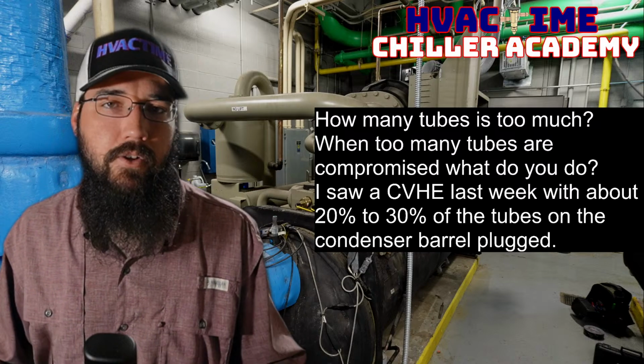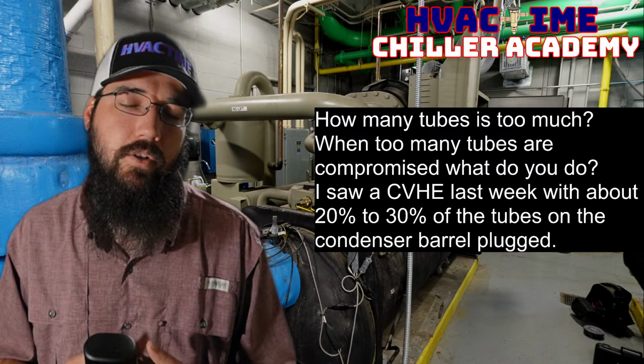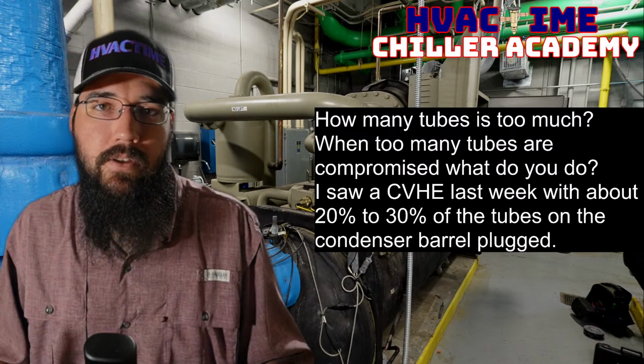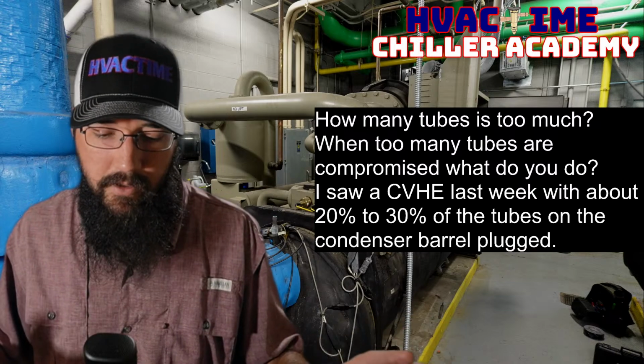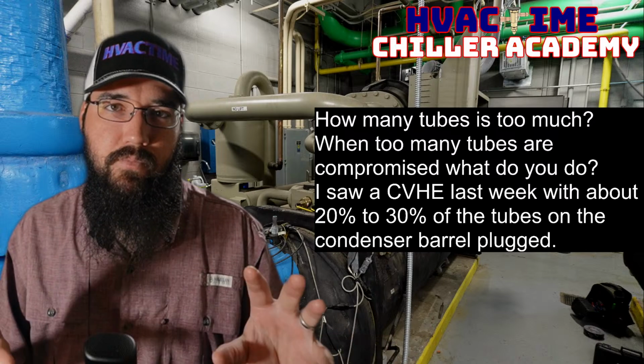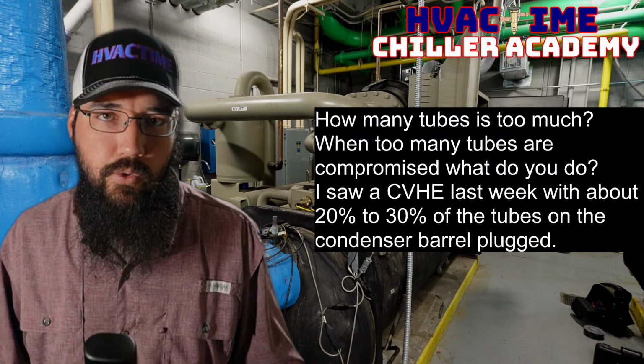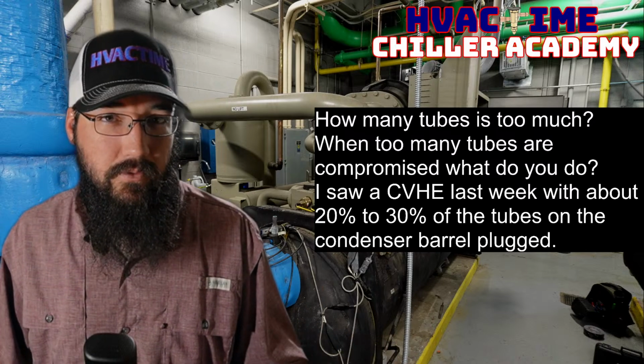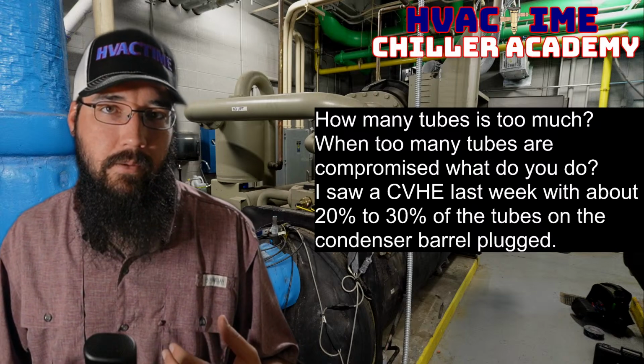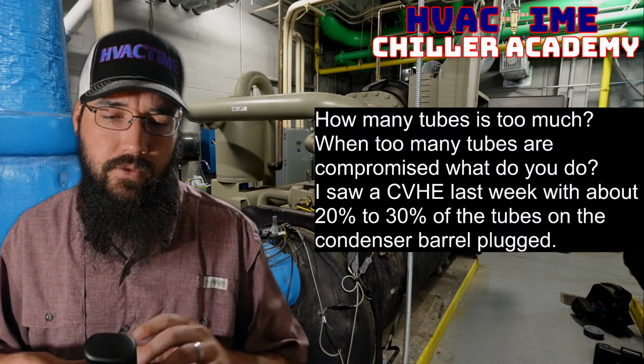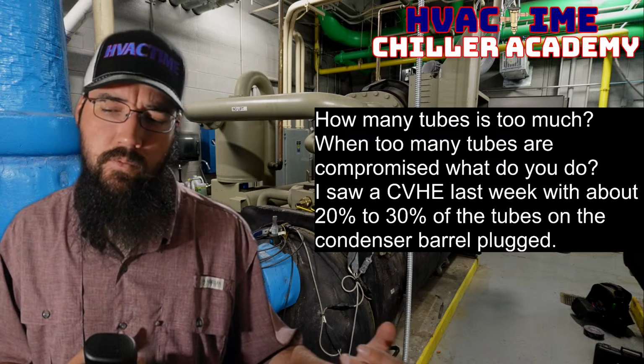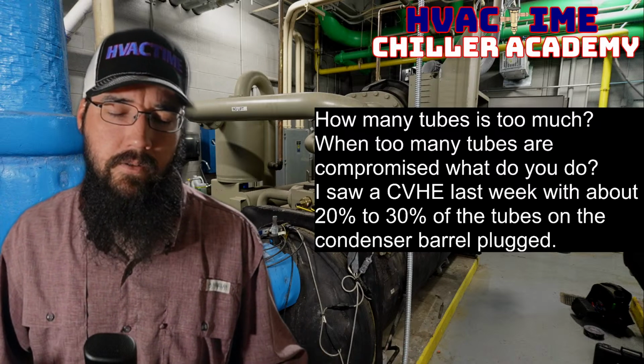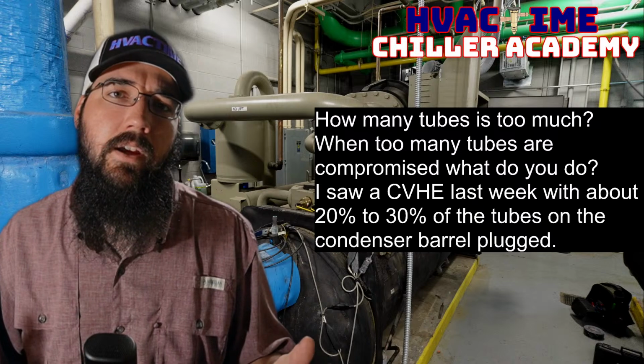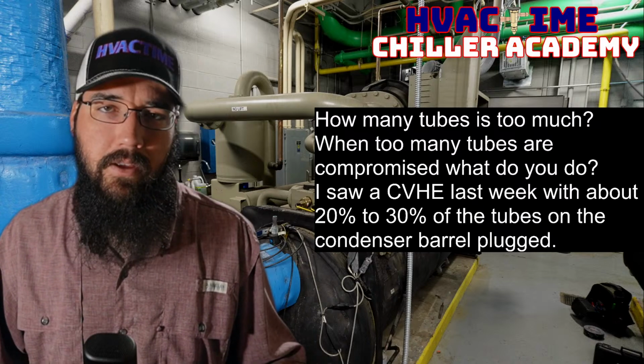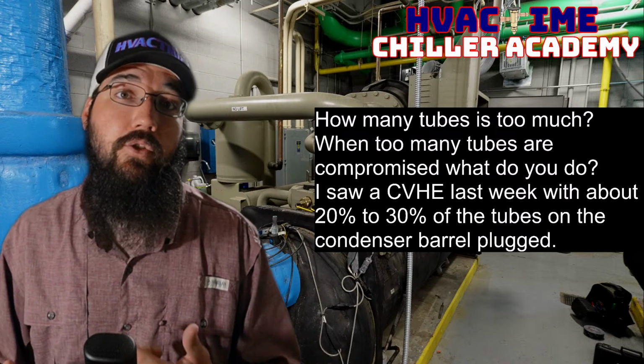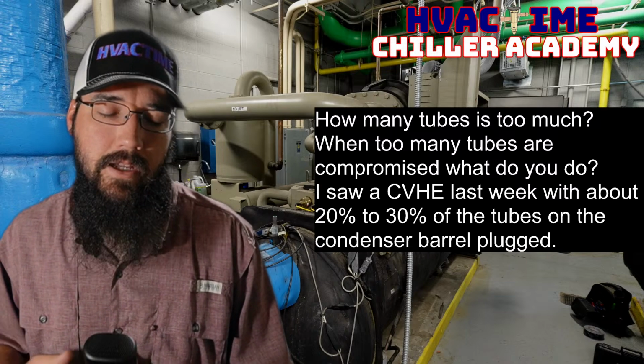And now, depending on your machine, maybe you could consider an overhaul condition at that point. Just depends on the circumstances, right? That's very, very situational. But retubing would be the next simplest step, and having a company come in, or your company if you do it in house, remove those old tubes, install new ones, flare them out on the end plates, and then you basically have a whole new set of tubes, and then you can get back into normal operation at that point.